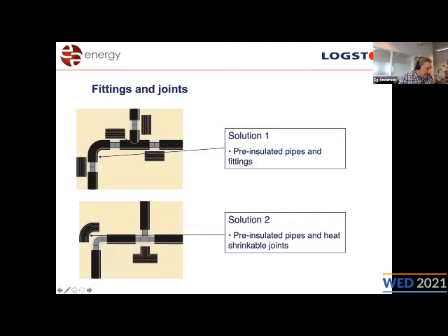So you have your T, where you branch off to a feeder system with your steam. Then you have the 2 pipes that you weld together. Then you put around half shells, and then the shrinkable joints go down there. Then you have a completely 100% sealed system. No water can go in nor out. And you can have it buried, you can have it above ground. It's good to last for a long time.